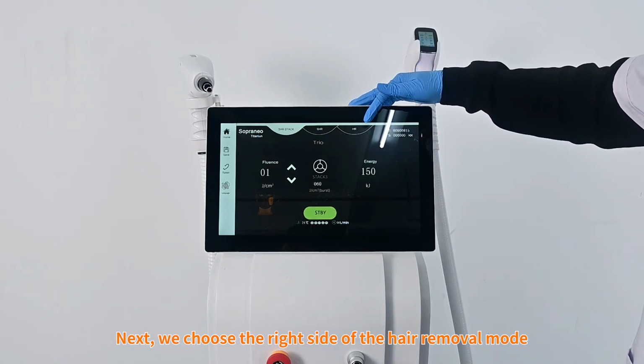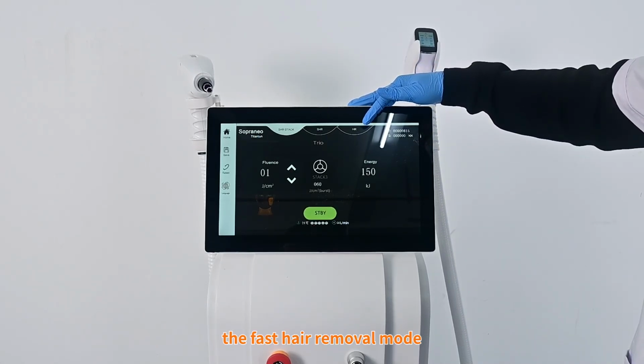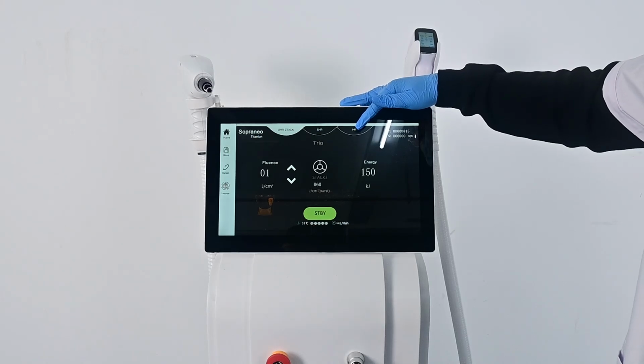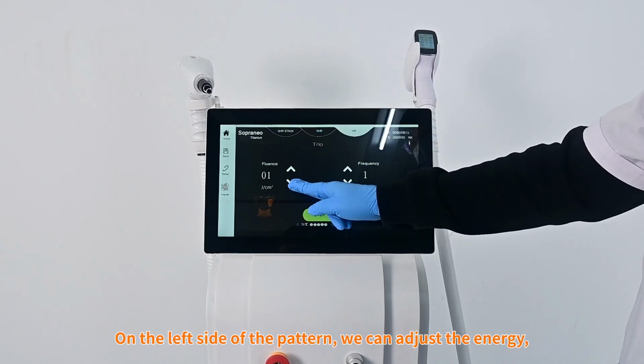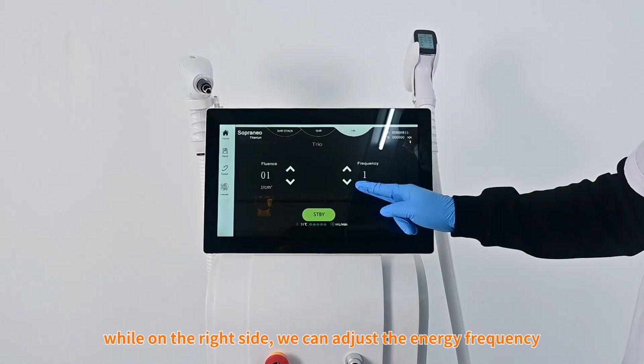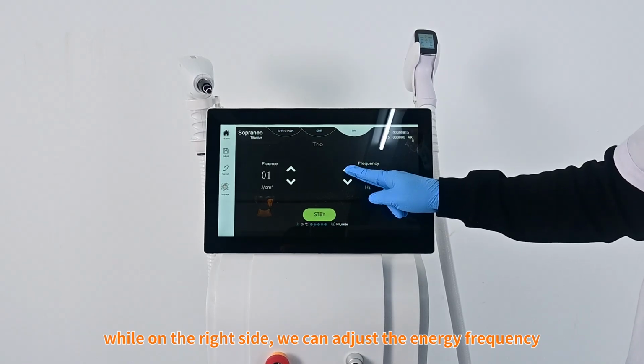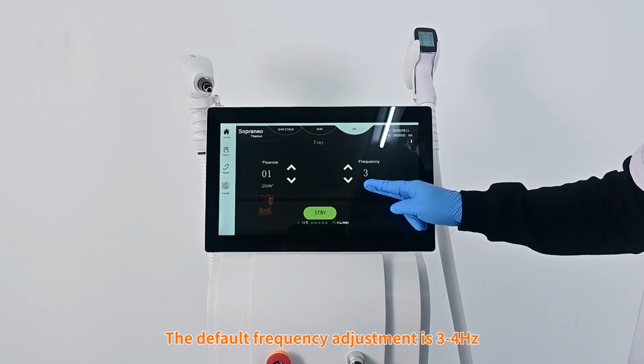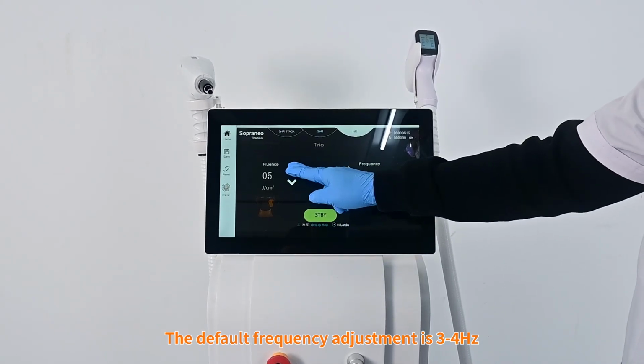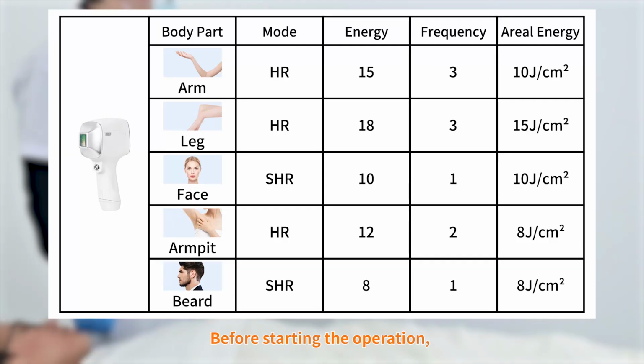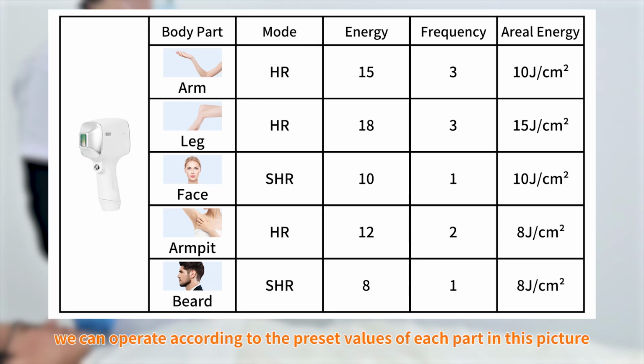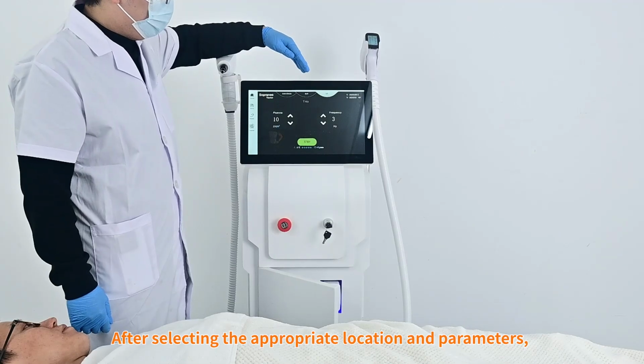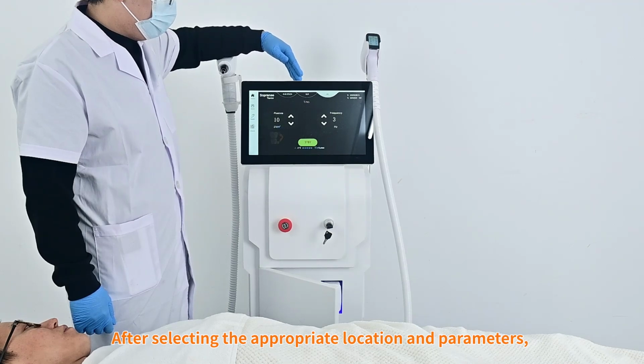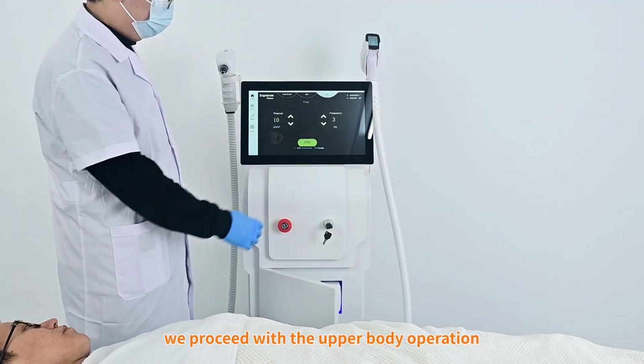Next, we choose the right side of the hair removal mode, the Fast Hair Removal mode. On the left side of the pattern, we can adjust the energy, while on the right side, we can adjust the energy frequency. The default frequency adjustment is 3 to 4 Hz. Before starting the operation, we can operate based on the preset values for each part in this image. After selecting the appropriate location and parameters, we proceed with the upper body operation.